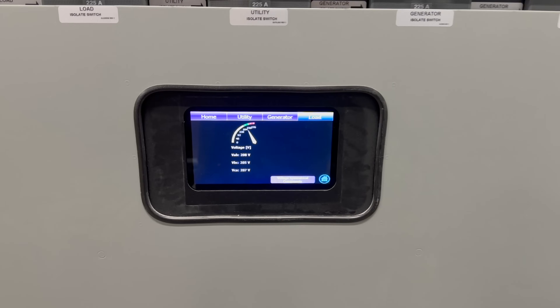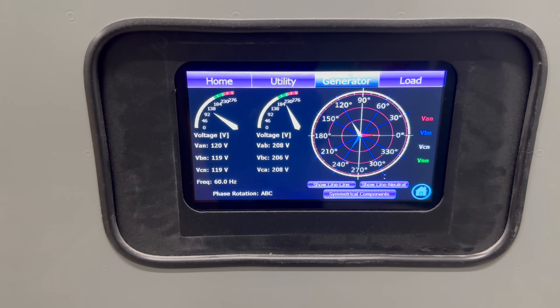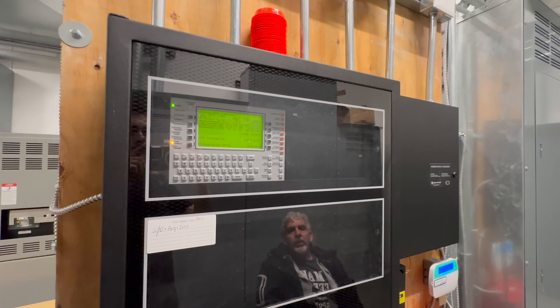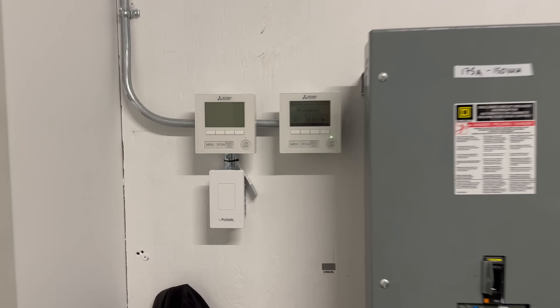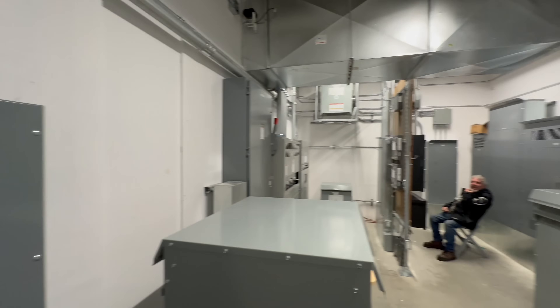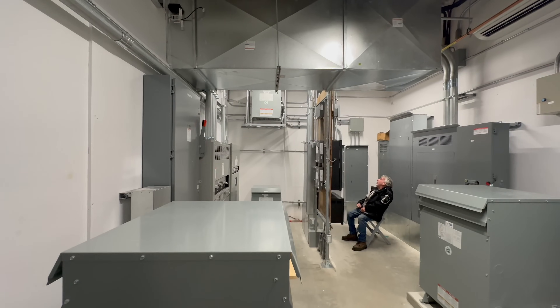Yeah, that's not the main. This utility is nothing — there's generator. There's no screen on this one anyway. Same in this school: the air conditioner is kept going in the electrical room, the other one's not. About 50% of the corridor lighting is kept up, stairwell lighting is all kept, and bathroom lighting is also kept — just not individual classrooms.